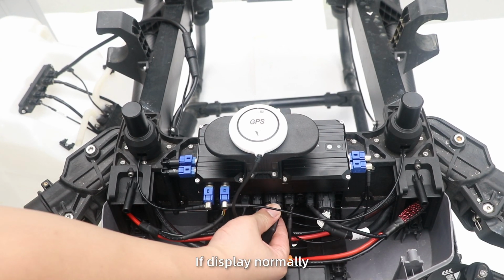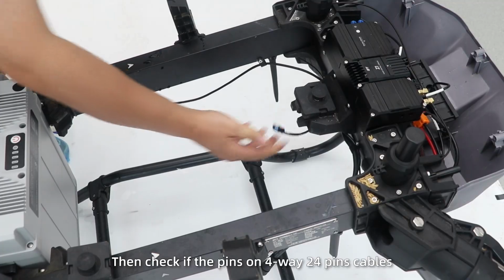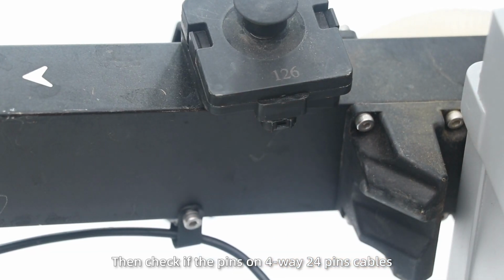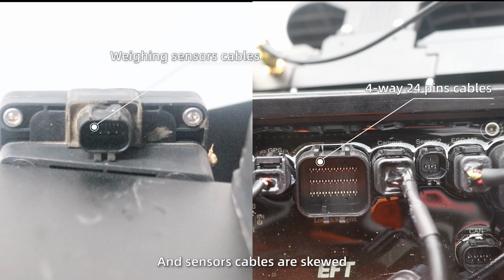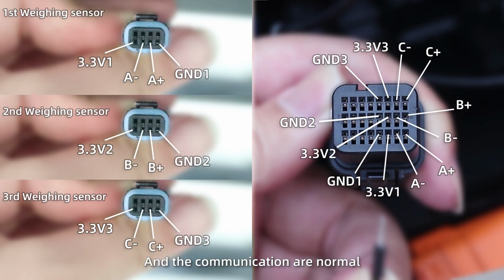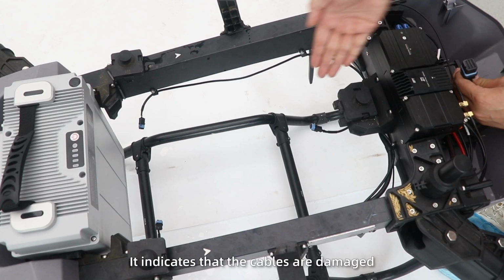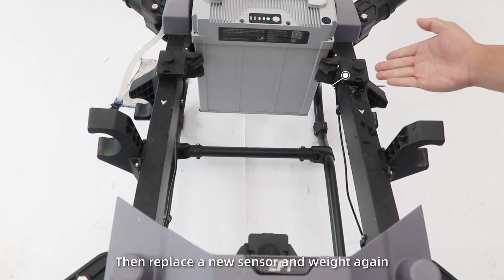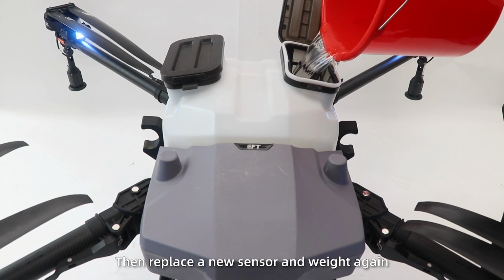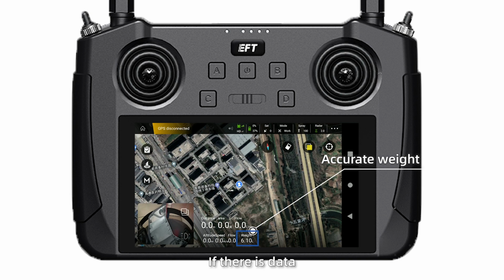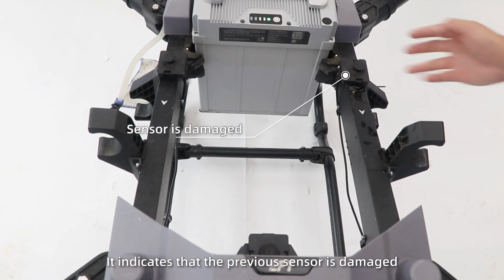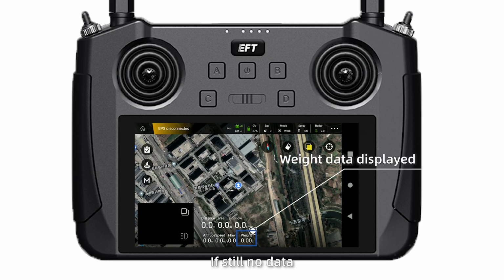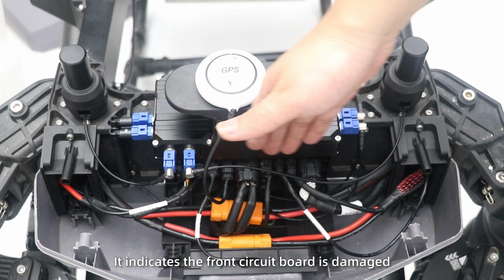If displayed normally, then check if the pins on the 4-way 24-pin cables and sensor cables are skewed and if the communication is normal. If they are abnormal, it indicates that the cables are damaged. If all normal, then replace it with a new sensor and test again. If there is data, it indicates that the previous sensor is damaged. If still no data, it indicates the front circuit board is damaged.